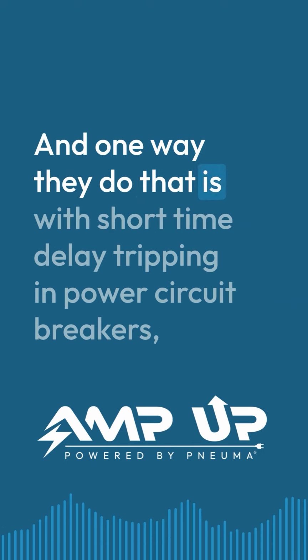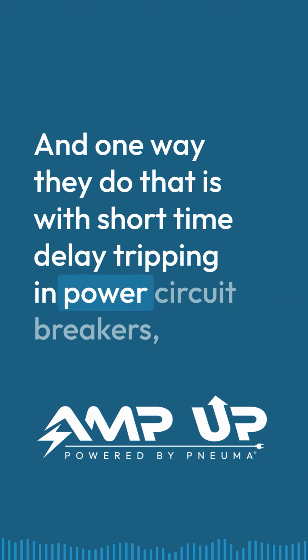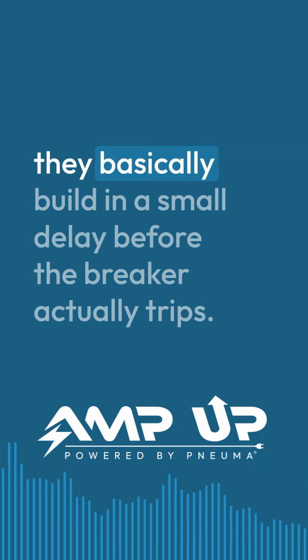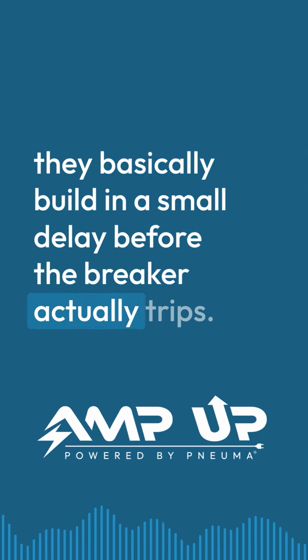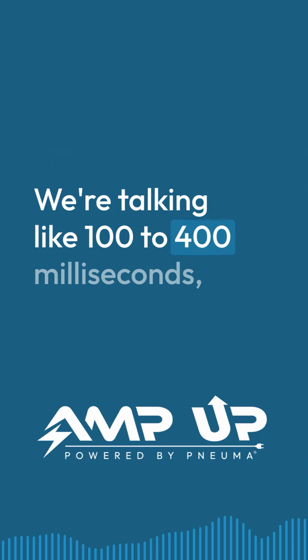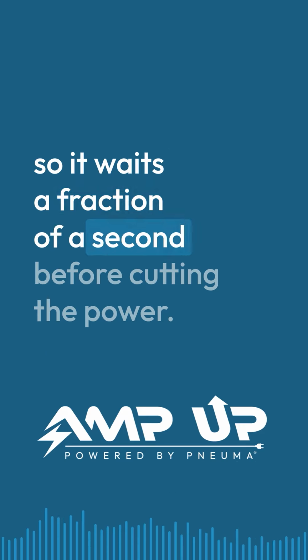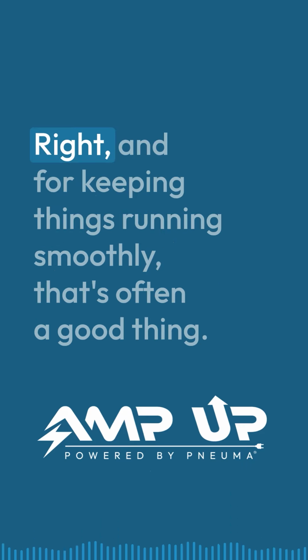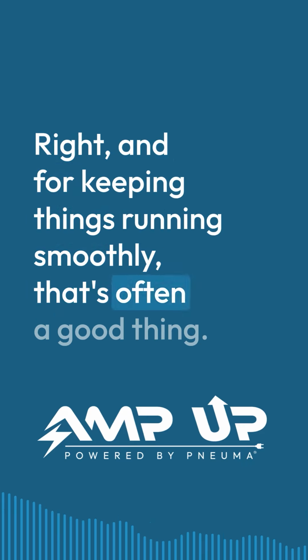And one way they do that is with short time delay tripping in power circuit breakers. They basically build in a small delay before the breaker actually trips. We're talking like 100 to 400 milliseconds. So it waits a fraction of a second before cutting the power. Right. And for keeping things running smoothly, that's often a good thing.